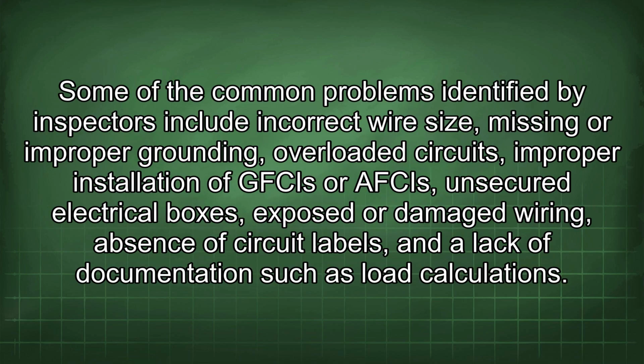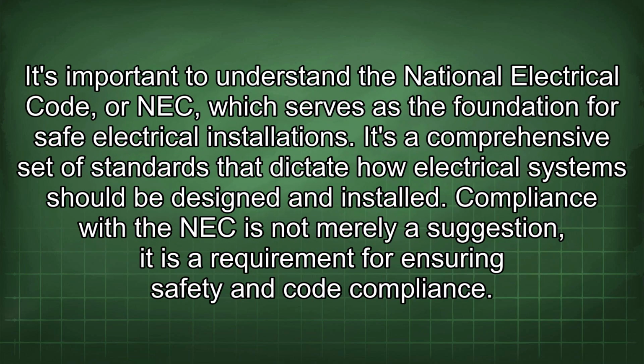Some of the common problems identified by inspectors include incorrect wire size, missing or improper grounding, overloaded circuits, improper installation of GFCIs or AFCIs, unsecured electrical boxes, exposed or damaged wiring, absence of circuit labels, and a lack of documentation such as load calculations. It's important to understand the National Electrical Code, or NEC, which serves as the foundation for safe electrical installations. It's a comprehensive set of standards that dictate how electrical systems should be designed and installed.